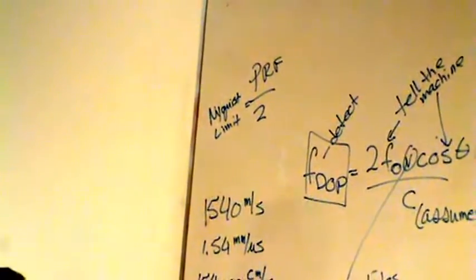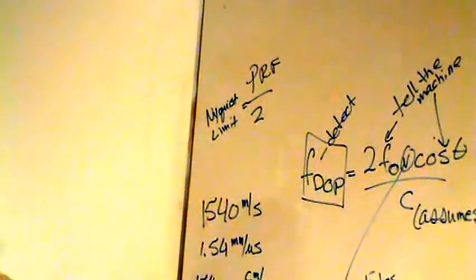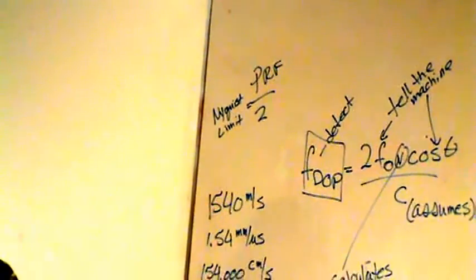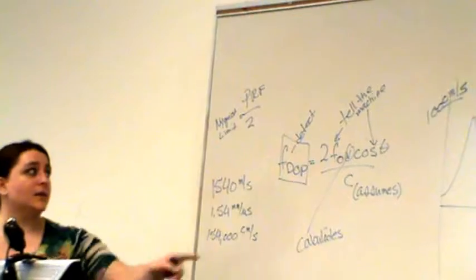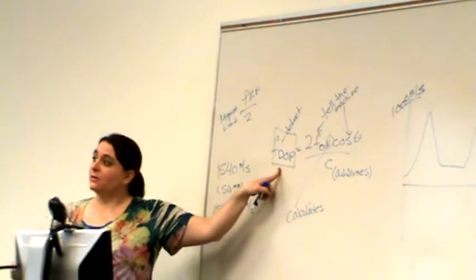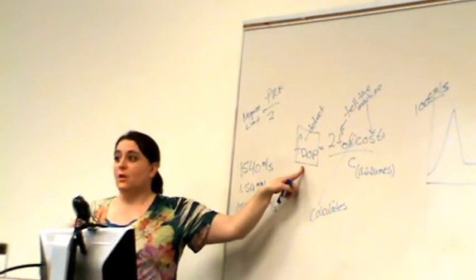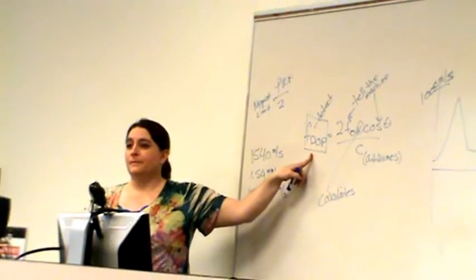So whatever that PRF is divided by 2, so if my PRF is 10 kilohertz, half of that would be 5 kilohertz. As long as this detected Doppler shift is 5 kilohertz or less, I'm not going to alias. If it's over 5 kilohertz, I'm going to alias.